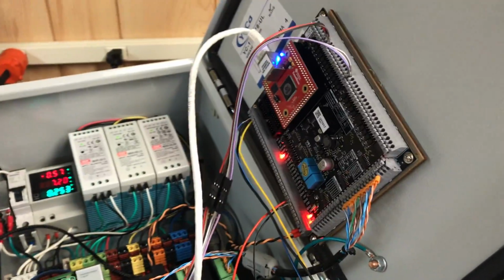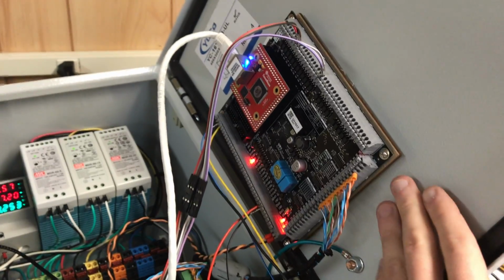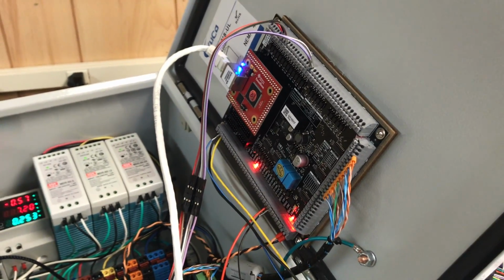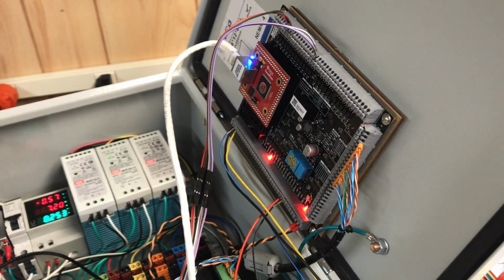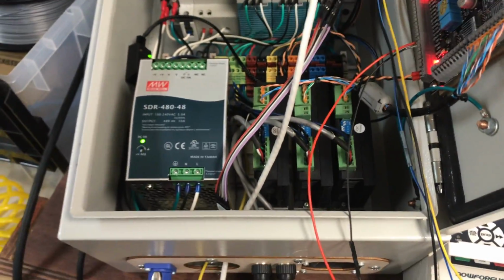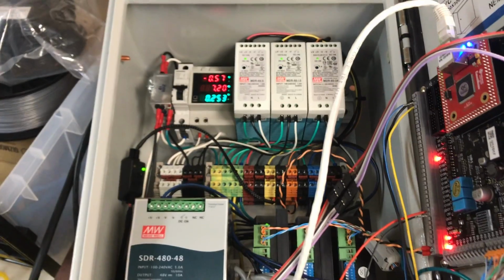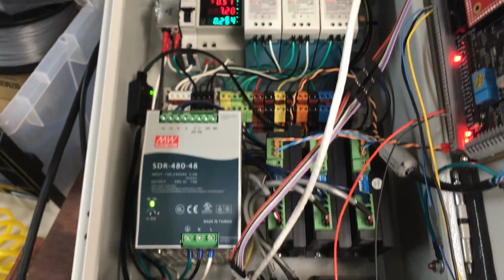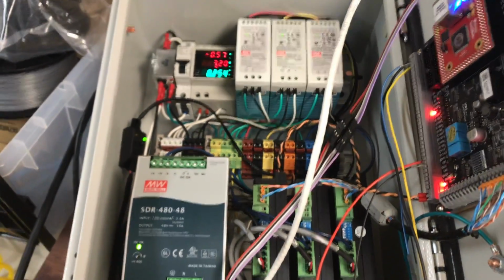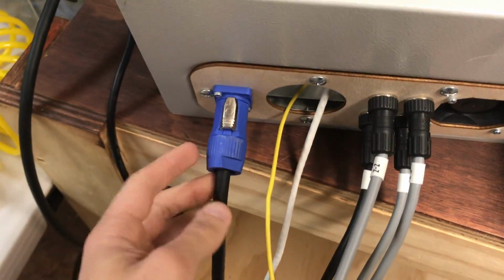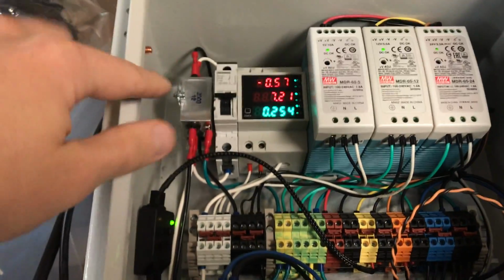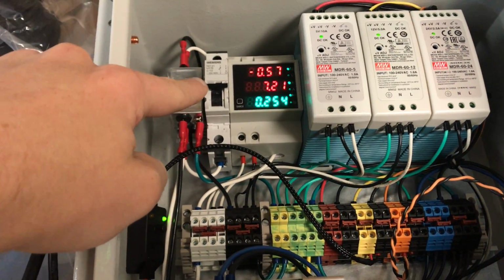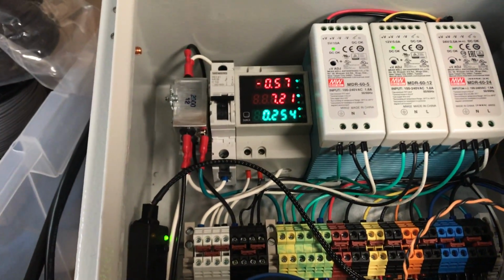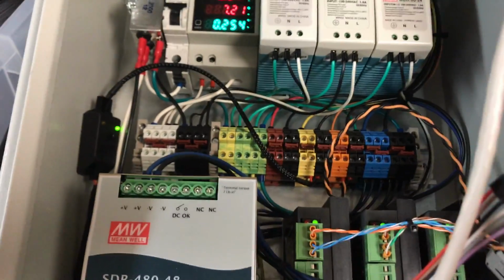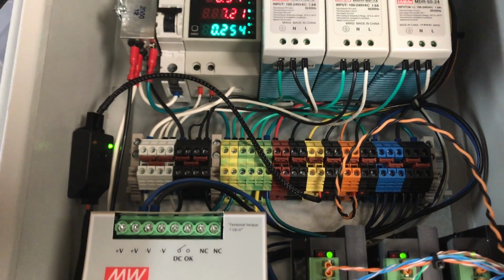Temporarily mounted is of course the UC300 Ethernet motion controller and the UB1 breakout board, and the inside of the enclosure is dominated, the majority of it, with the power distribution. So we have the Neutrik powerCON connector for the line in that then goes through an inline EMI filter, which then goes to a Siemens 10 amp breaker. And that's where the live hits the terminal blocks.